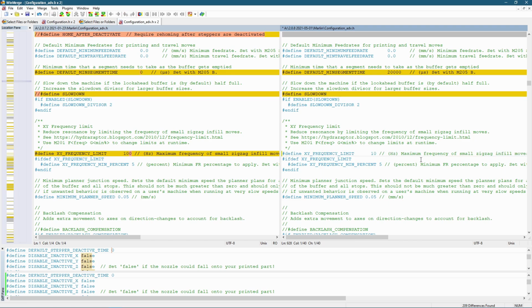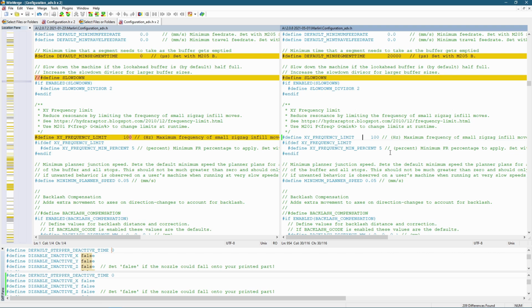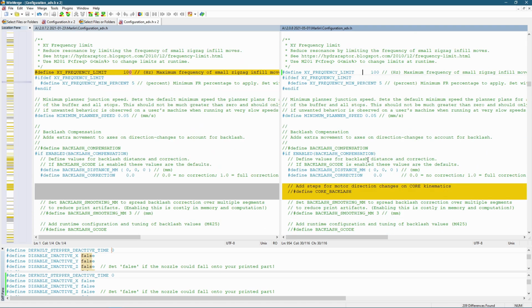Okay, now this is a nice setting I do like to have on, which is the frequency limit. If you set this to a nice value, it starts out as low as 10, but I find it slows my machine down too much. This just prevents your machine from oscillating at high frequency rates. So a 10 hertz means that 10 times a second it can change direction, and any faster than that, it will slow down. So yeah, leave that one enabled at about 10 hertz, and then if you find you're having issues, you can actually increase it through the LCD menu.